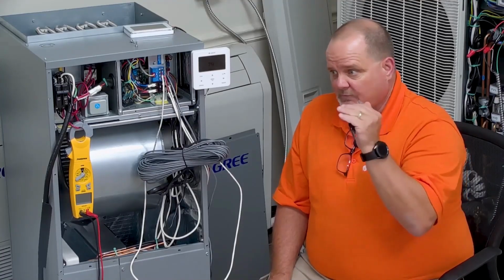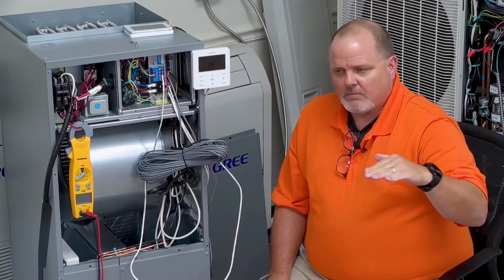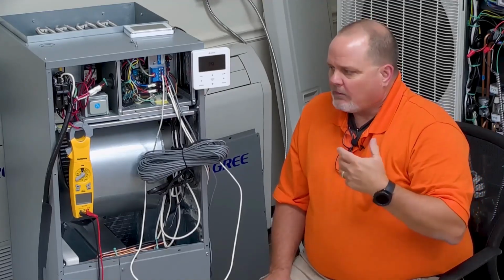So in other words, basically the first stage or the second stage gets satisfied, electric heat drops off, heat pump stays on. Let's say the temperature drops a little bit again, then the auxiliary heat comes back on, and then that part of it gets satisfied, goes back to running the heat pump, and it can just keep cycling like that, keeping that heat pump running the entire time, somewhat maintaining the temperature with a little help, okay? Like I said, you have the option to set it up either way. You can make it just satisfy the thermostat and shut the whole system down, or you can set it up to where auxiliary heat only cycles in when it needs to.